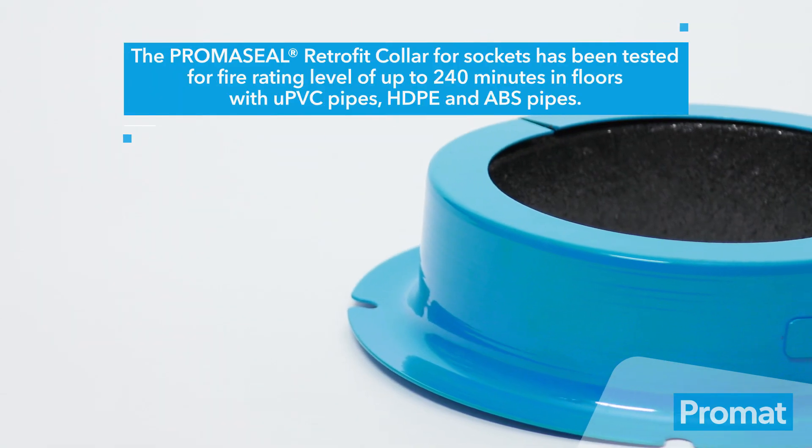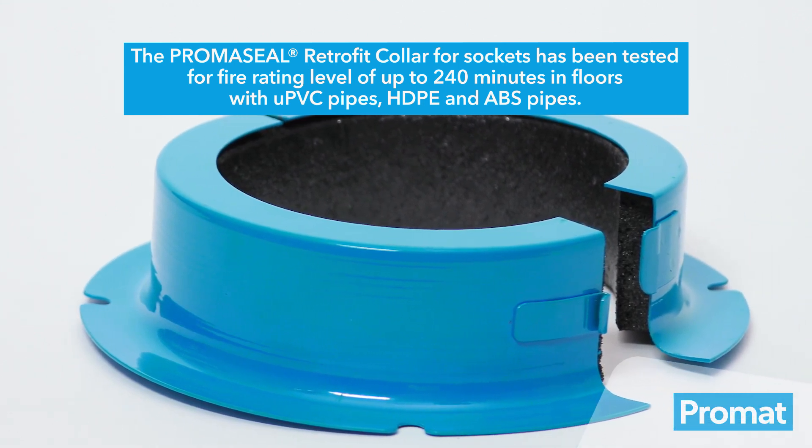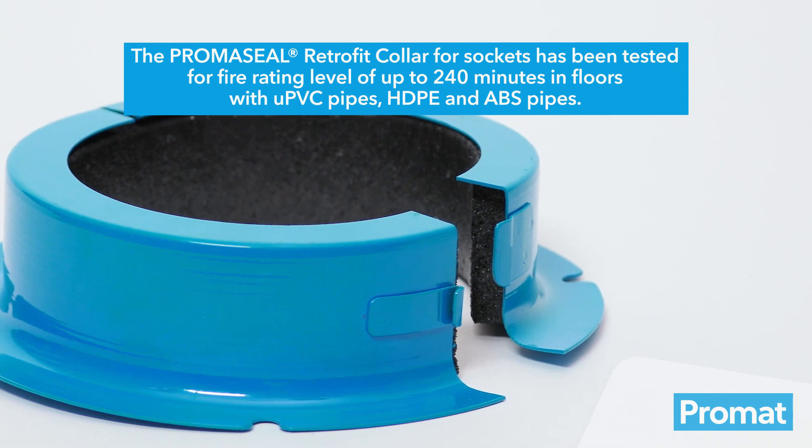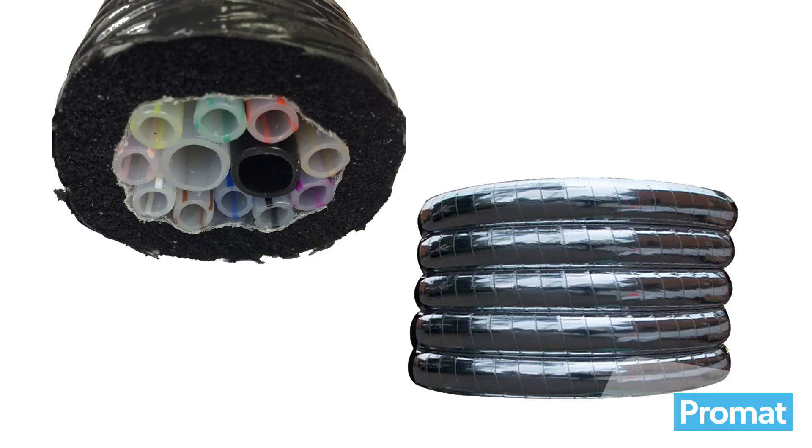The PROMASEAL Retrofit Collar for Sockets has been tested for a fire rating level of up to 240 minutes in floors with UPVC, HDPE and ABS pipes. It can also be used on floors and walls for post-mixed drink lines or beer pythons, with a fire rating level of up to 120 minutes.